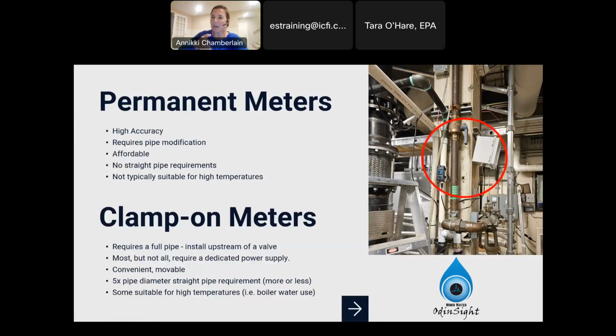The system comes on and it's reading flow and then it closes, but the pipe is not empty because it's sending a sound signal through there. It's ultrasonic. Most of them require a dedicated power supply, so that can be really limiting in irrigation. So both the straight pipe and the power supply can be limiting in irrigation, but they're super convenient. This one is actually at a hospital and they have a bunch of them and they love them because they just move them around. So if the cooling tower is shut down, they can go put it on other water lines and processes and see what's going on.